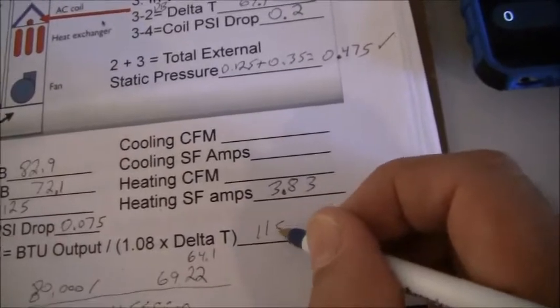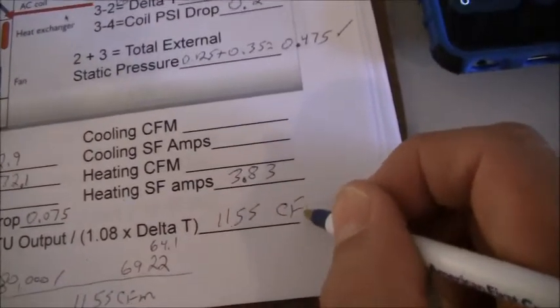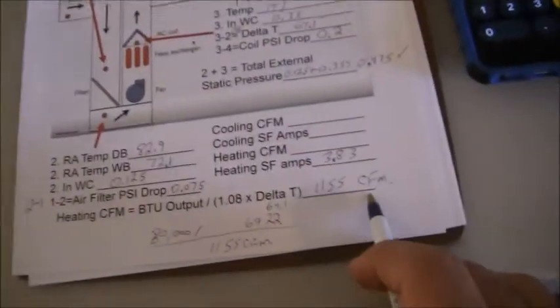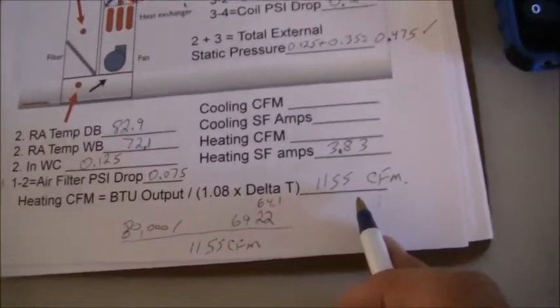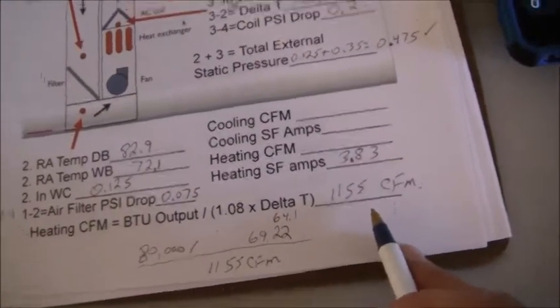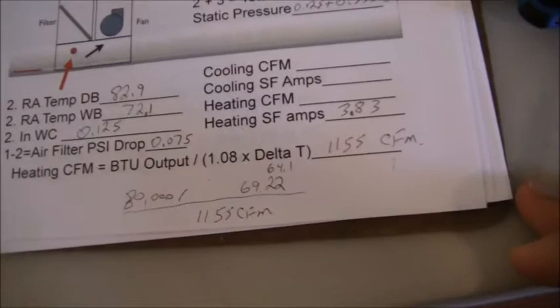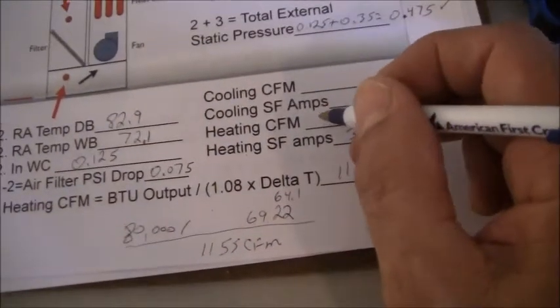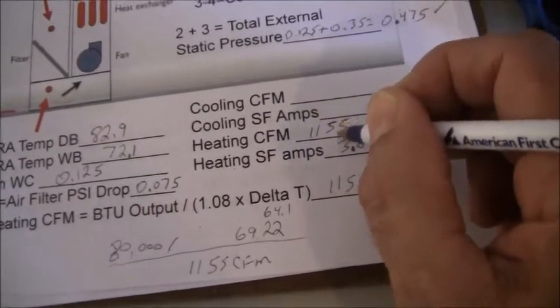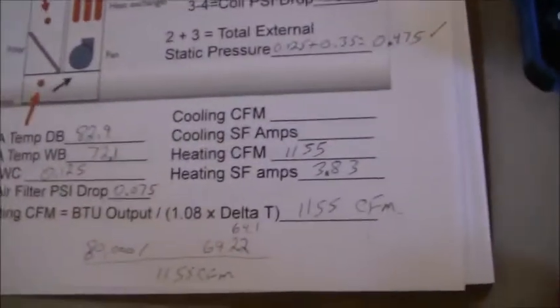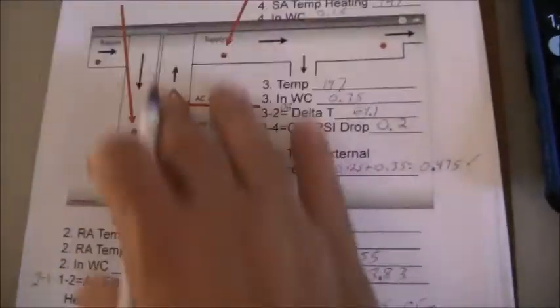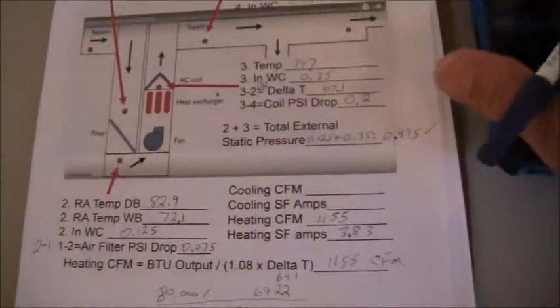Okay, 1155 CFM. So now we know what the heating CFM is. We'll compare that against the cooling CFM once we get into the cooling. But the heating CFM is 1155. So this is just helping us fill out our sheet and get all of our data. Next thing we want to do is wait for the system to cycle down, and then we're going to throw the unit on in cooling and get that going. This is still cycling down. The fan hasn't shut off yet, so we're still not below 95.